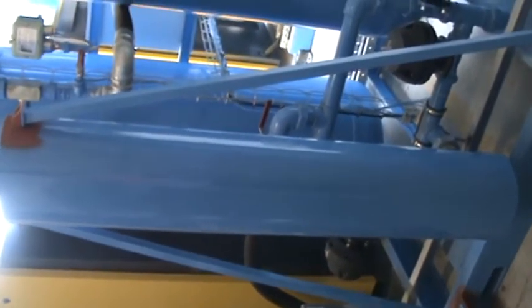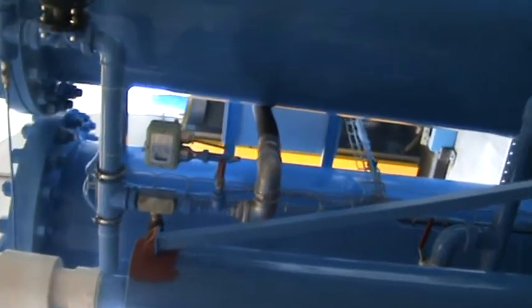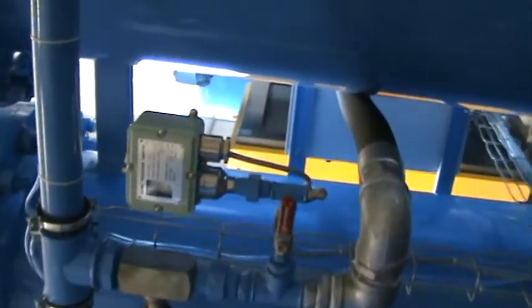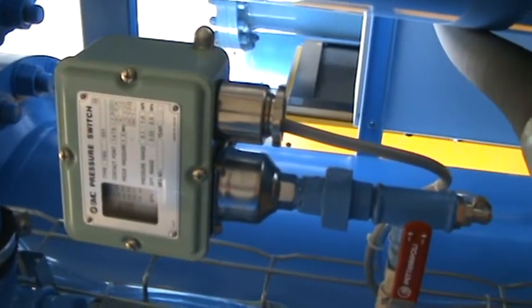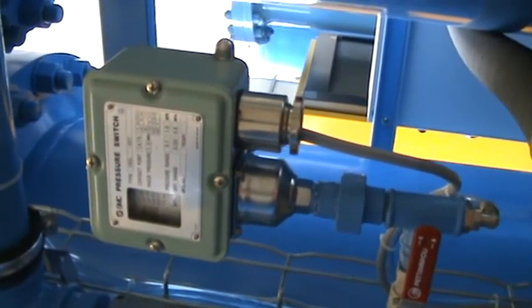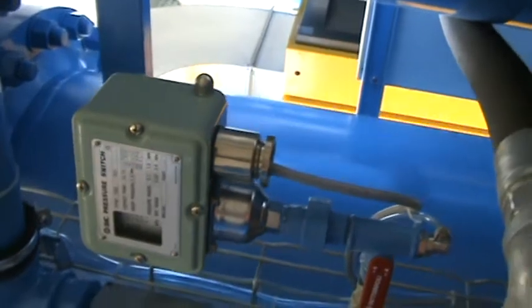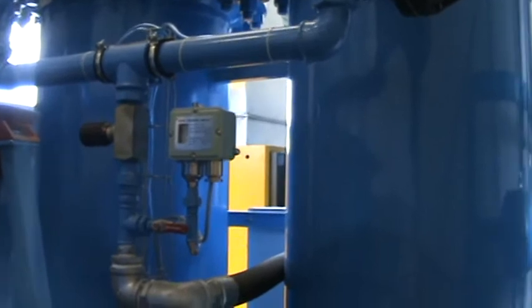Then we have an exhaust valve silencer valve with the two turrets as you can see there. There is also an automatic pressure relief safety valve at the outlet which can be adjusted to suit the customer's requirements. In the event of a colleague worker turning off a valve to a CA room without turning the PSA unit off first, the machine will automatically shut down as soon as the pressure builds 0.2 PSI or whatever the set point is.